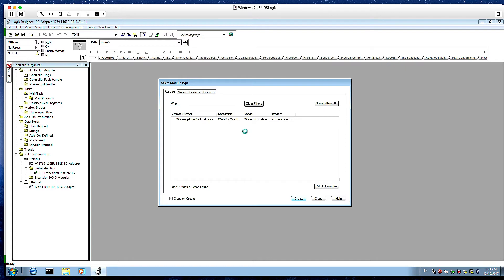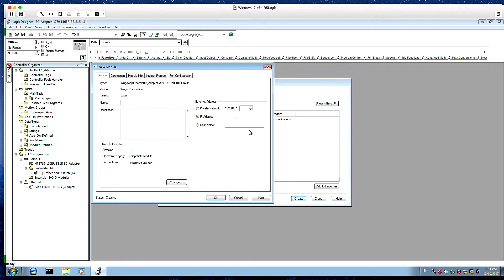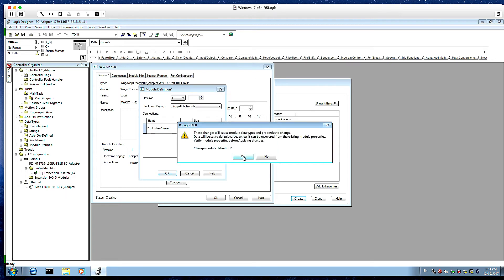And you can search for WAGO in the field. Select the EDS file. And so this is very straightforward. All we need to do is we need to give it a name. We'll call this WAGO PFC. We need to give it an IP address. And then we need to change the size. So if we click this change button, it defaults to 32 bytes in and out. We're just going to change this to 10 based on the size of our function block. Click OK. And now we're done. We've added the device.